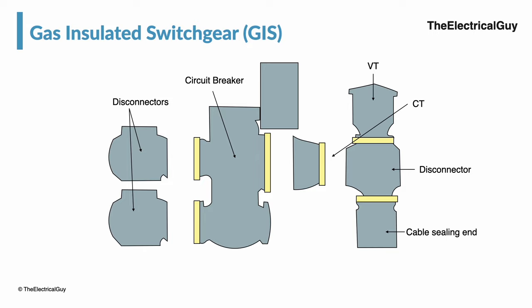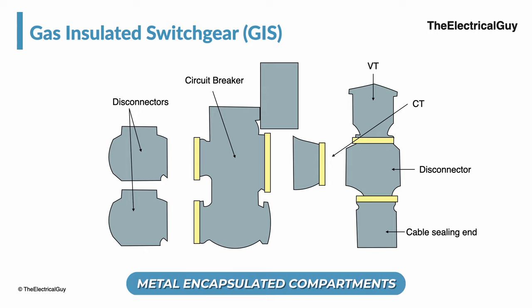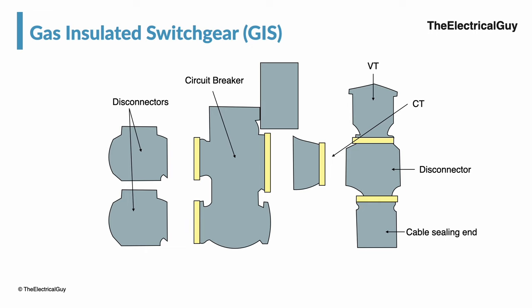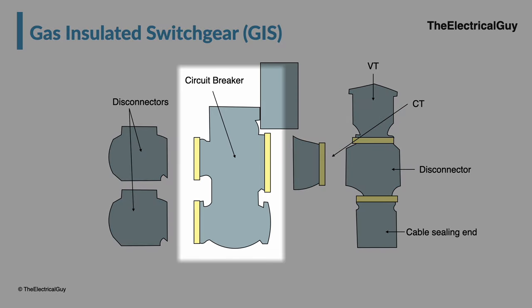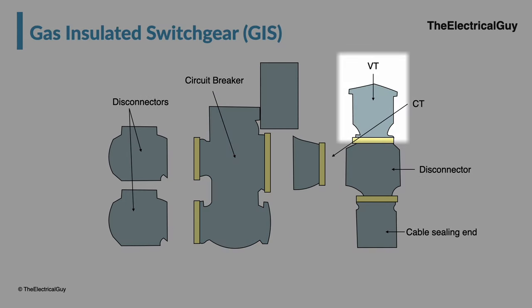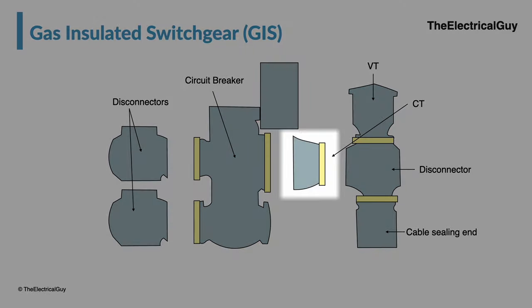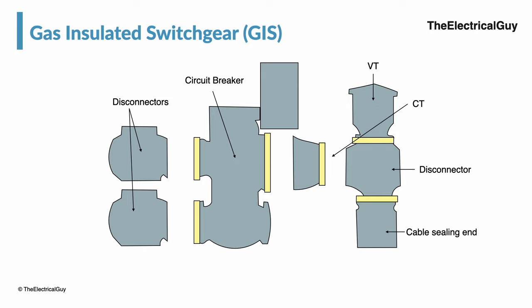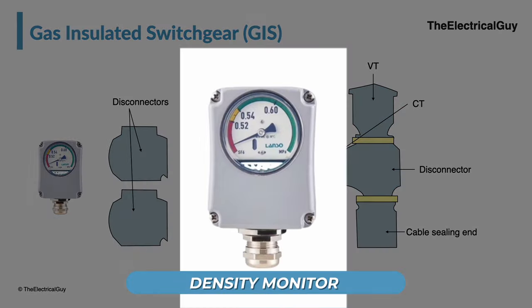All the switchgear are placed in metal encapsulated compartments. Further, GIS is subdivided into different modules or zones. For example, the circuit breaker will have its own dedicated module. Similarly, the voltage transformer, current transformer, and all other switchgear will have their own separate modules. The bus bar will have its own module as well. Each module will have SF6 gas filled in it, and the SF6 gas pressure inside each module can be monitored separately using a dedicated density monitor provided with each module.